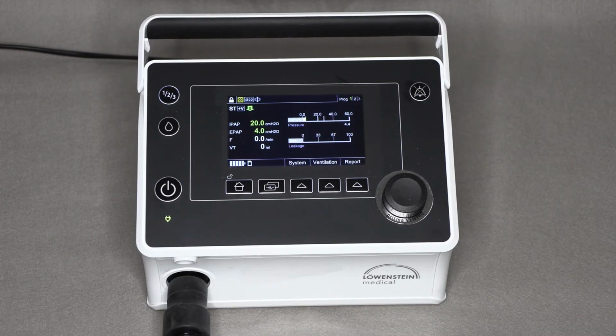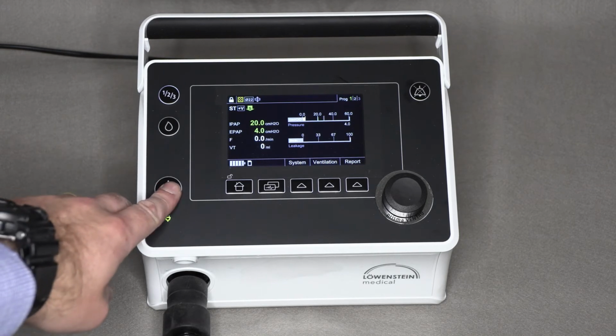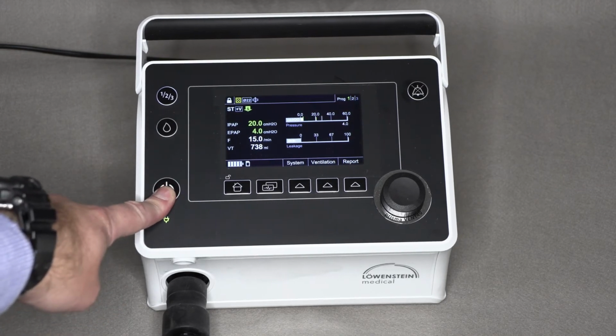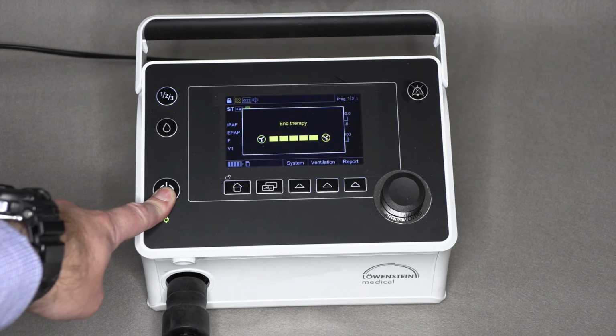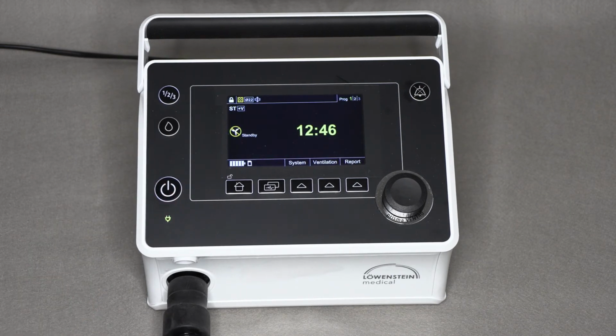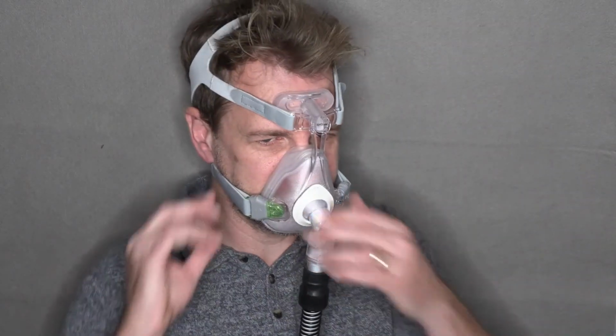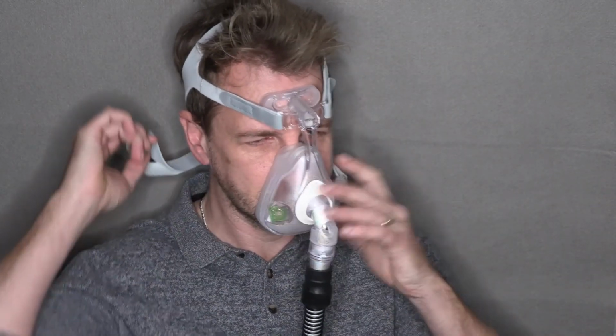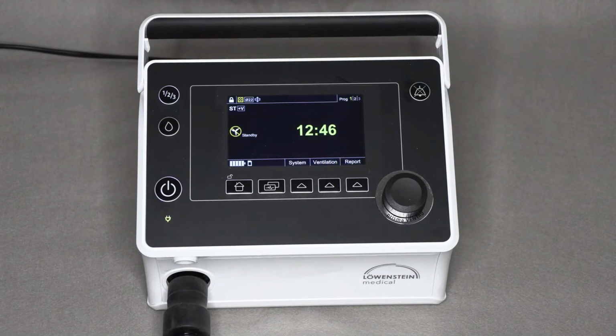In the morning time, or whenever you want to stop therapy, to turn off prismaVENT, simply press and hold the large power button until the progress bar goes all the way from left to right. The mask can now be removed if you haven't already removed it. It's always best to leave the device plugged in and connected to electrical power even when it's not in use, as this ensures the battery is kept full for a time when you may need to rely on it.